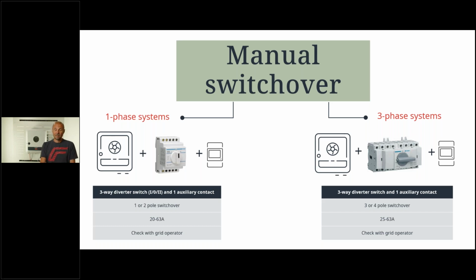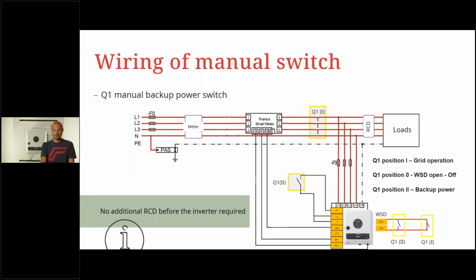So that's a rather simple solution, not expensive, so really a good idea for all the customers who would like to save money. The wiring is also quite simple. You see Q1 is this manual switch where we switch off the 3 phases in this case, and maybe also the neutral. So this is the 3-pole switch over where we switch off only 3 phases. We need a feedback to input 6 and input 7, a 12-volt signal from this switch when we are in position 2, or backup power mode position.